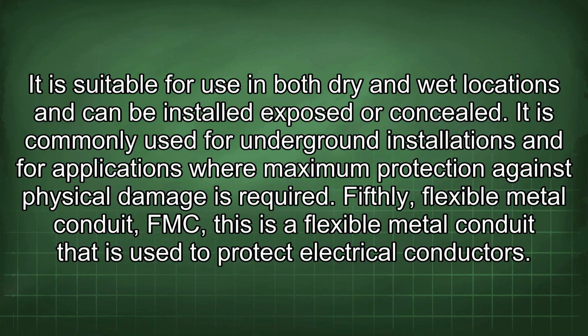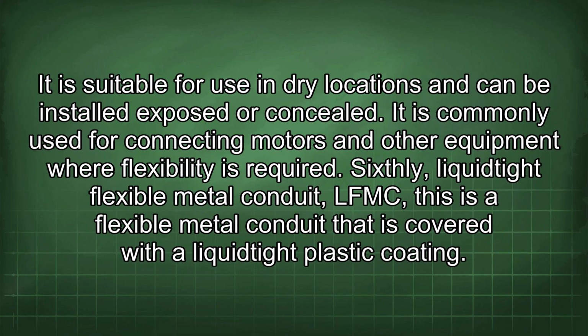Fifthly, flexible metal conduit, FMC. This is a flexible metal conduit that is used to protect electrical conductors. It is suitable for use in dry locations and can be installed exposed or concealed. It is commonly used for connecting motors and other equipment where flexibility is required.